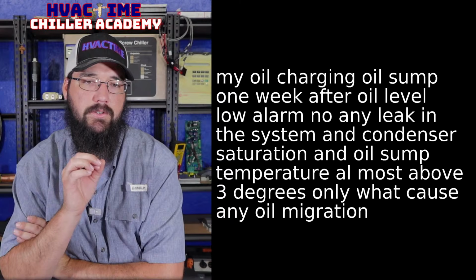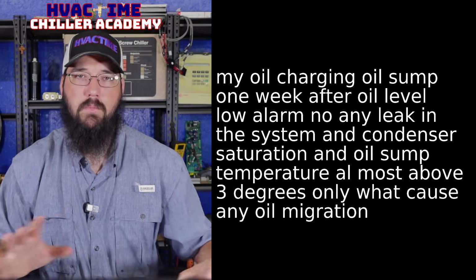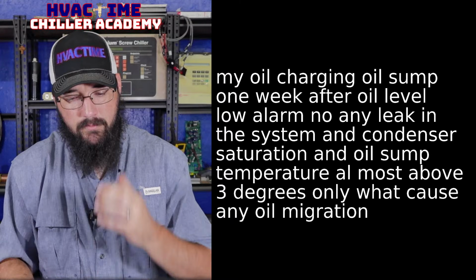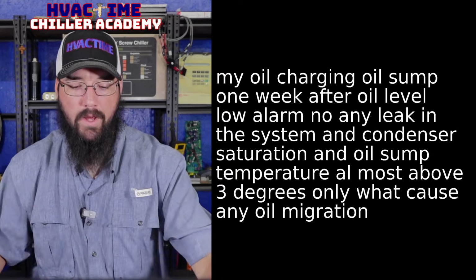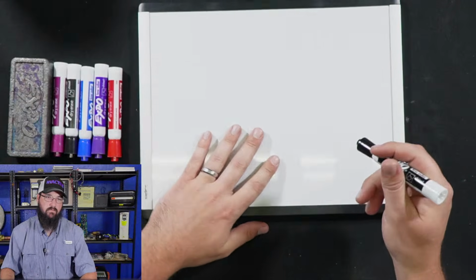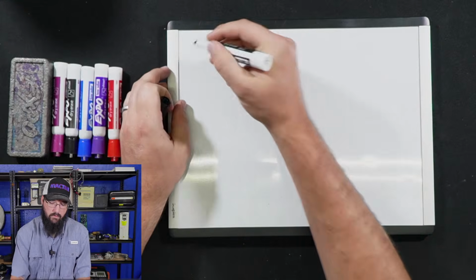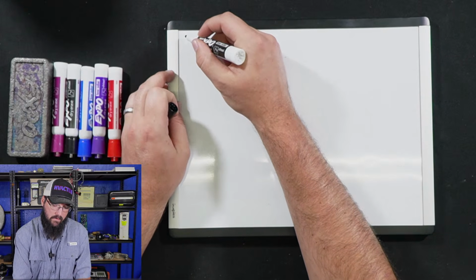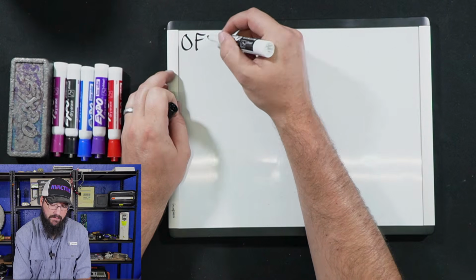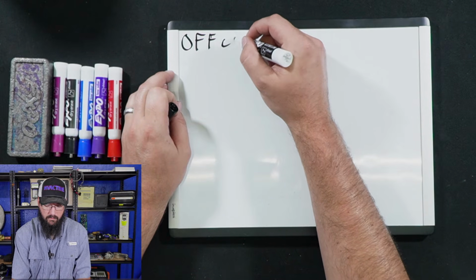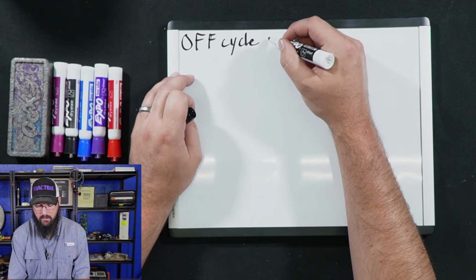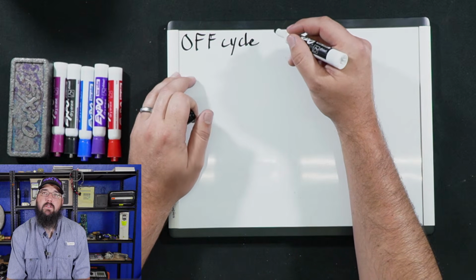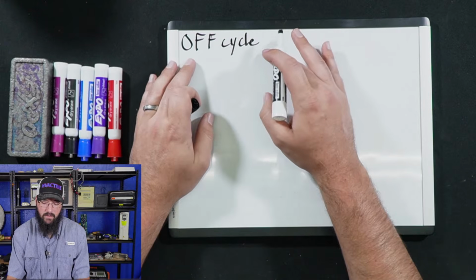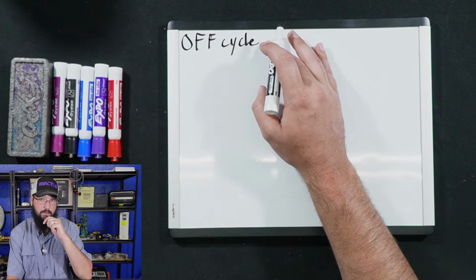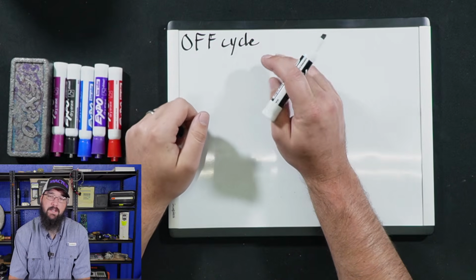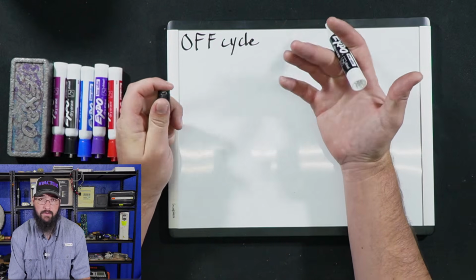The oil charge. How about we just take a migration approach in general? What are different ways we could have a migration event? So one would be in the off cycle. We could have an off cycle migration. This could even be true, excuse me, depending on the machine, even if you have oil heaters functioning.